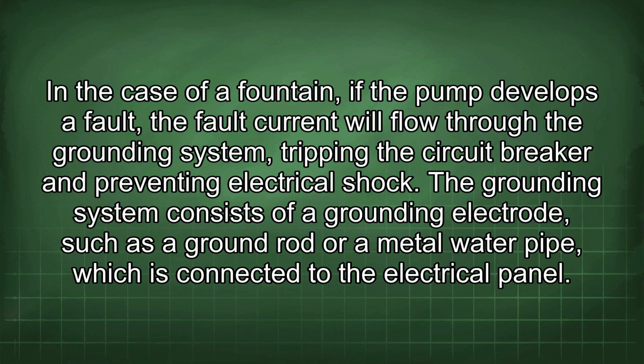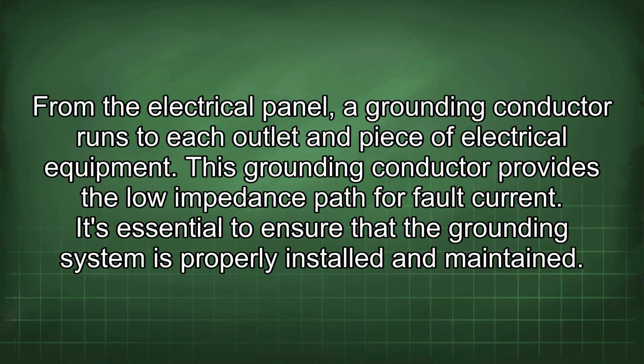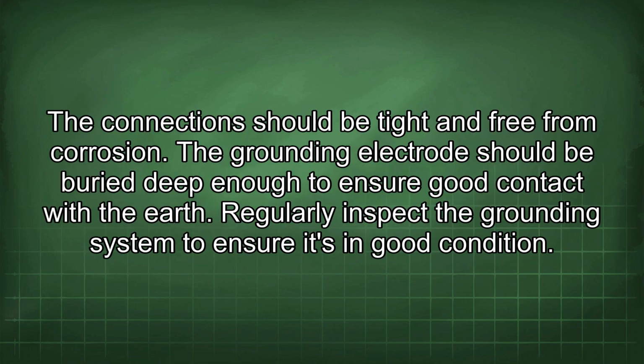The grounding system consists of a grounding electrode, such as a ground rod or a metal water pipe, which is connected to the electrical panel. From the electrical panel, a grounding conductor runs to each outlet and piece of electrical equipment. This grounding conductor provides the low impedance path for fault current. It's essential to ensure that the grounding system is properly installed and maintained. The connection should be tight and free from corrosion. The grounding electrode should be buried deep enough to ensure good contact with the earth. Regularly inspect the grounding system to ensure it's in good condition.